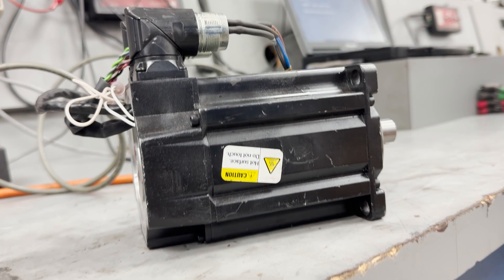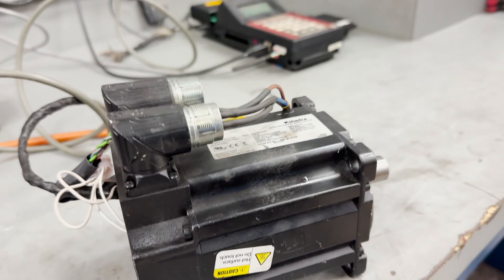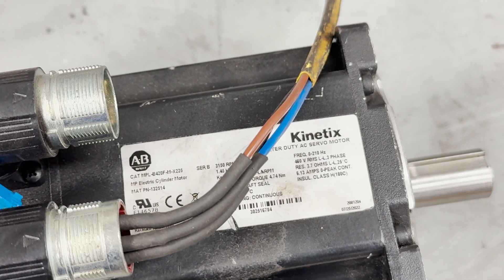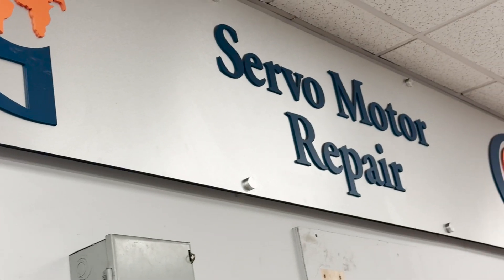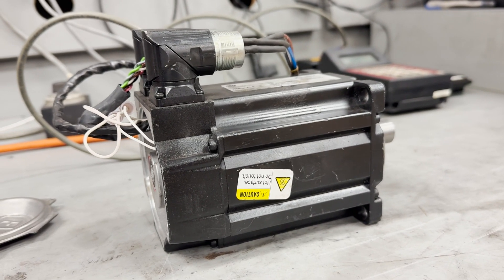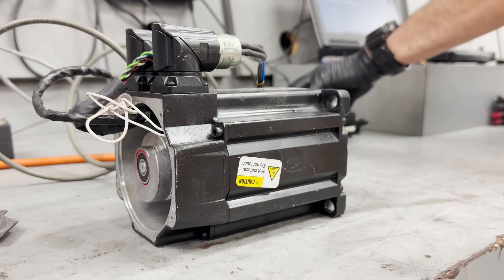Hello. In today's video, we'll take a look at an Allen Bradley Kinetix servo motor that a customer sent in for service. The customer reported excessive vibration, which they believe is caused by failed bearings. However, we'll uncover a deeper issue: a faulty encoder.